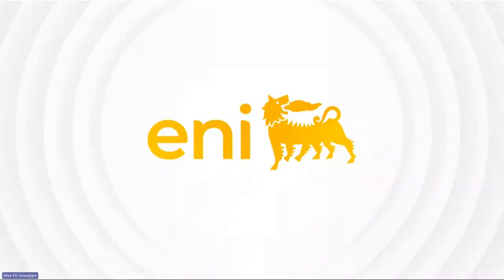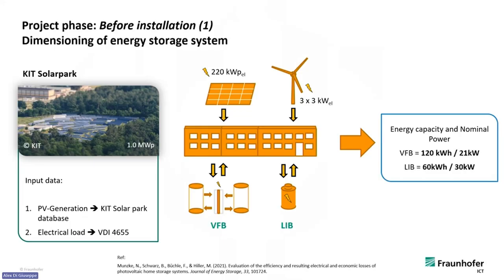So too much actually to generate it to support this place. The task was first to lay out the vanadium battery and storage. So we decided to have a 21 kilowatt, 120 kilowatt hour flow battery and a 60 kilowatt hour, 30 kilowatt lithium-ion battery. It's phenomenal.